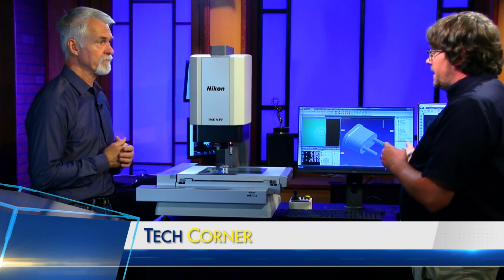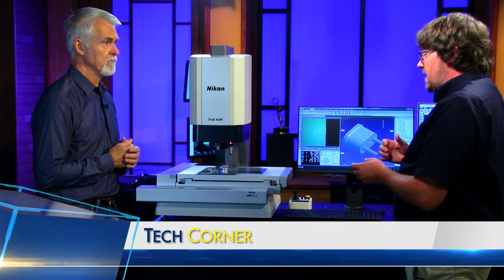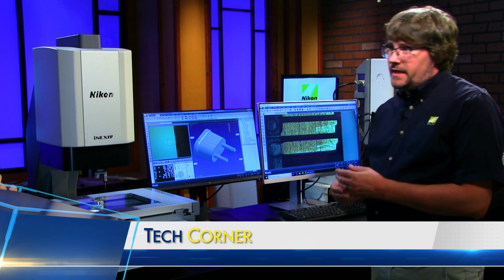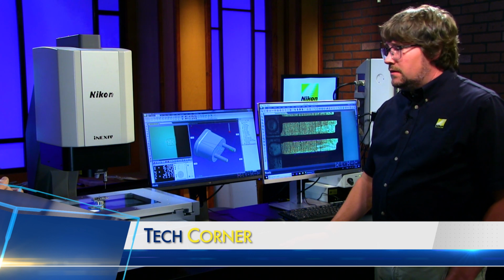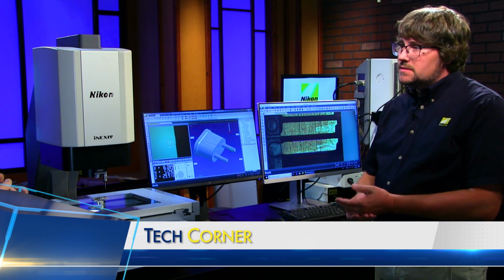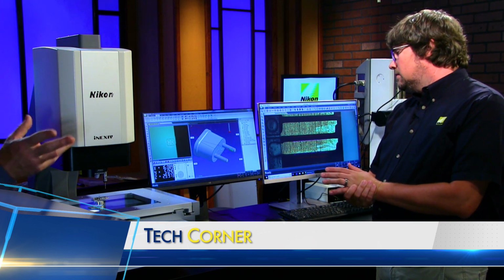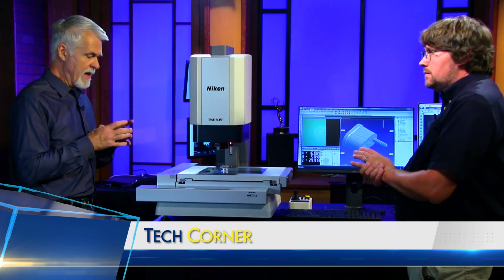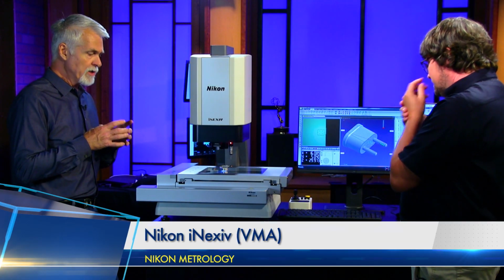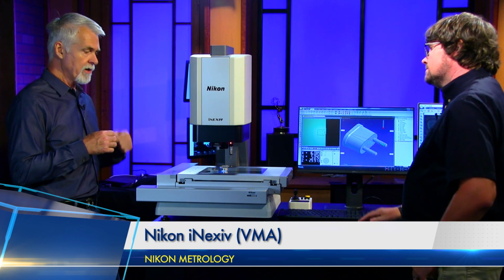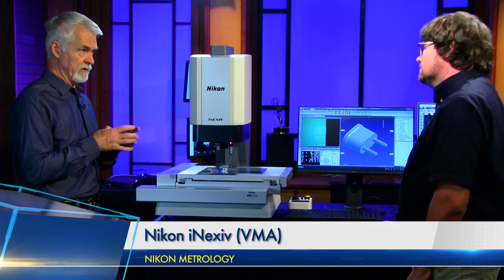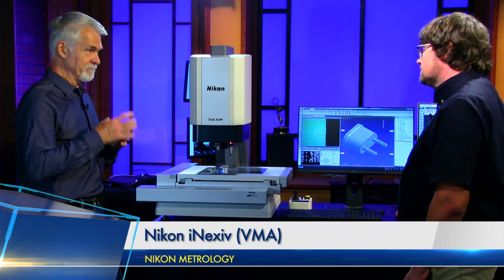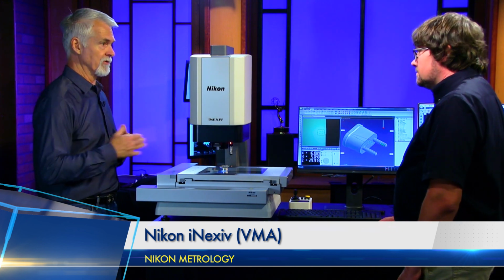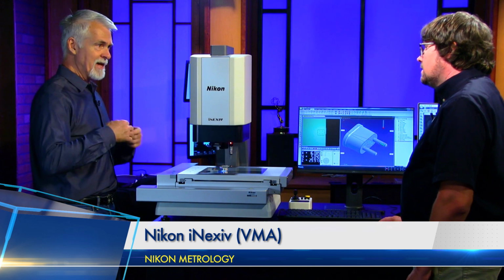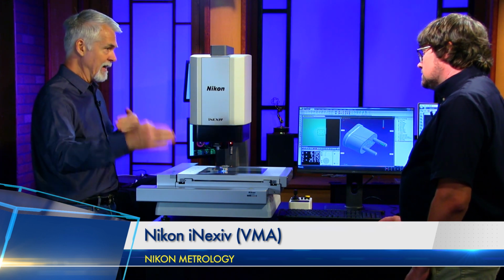Yeah, so the nominal CAD model of the part, along with models of things like probe racks or rotary indexers or other so-called obstacles that might be on the stage, are all avoided automatically when you're creating paths. Okay. Now, I think I already saw you do it here, but if you're going to take a measurement and your starting point is within one field of view and your ending point is in another field of view, you have to traverse the stage. Does that affect measurement at all, or is it all calibrated together?